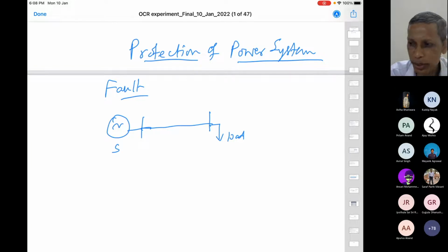But suddenly, due to insulation failure also, at times, not always, not very common, some fault happens. So when I say fault, it means a typical short circuit. It can be an open circuit also, but in an open circuit condition, current will not be detrimental. During a short circuit, the phase conductor touches the ground, or the phase conductor touches the neutral conductor, due to insulation failure or any metallic path, and the metal is already connected to the ground. So what will happen?